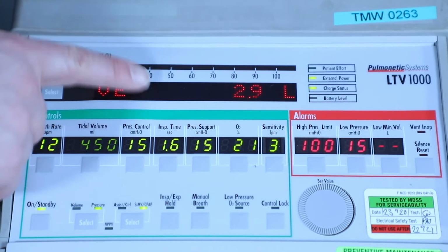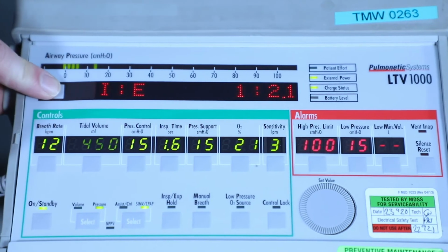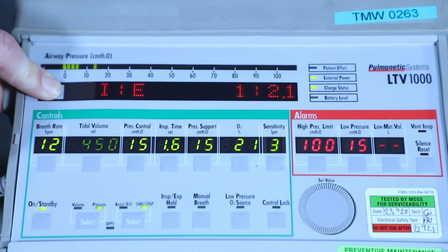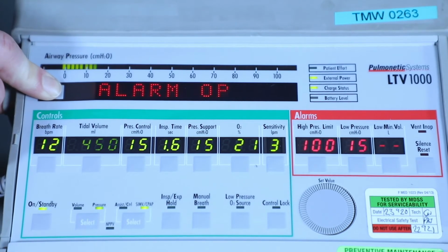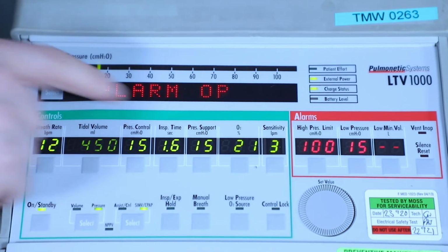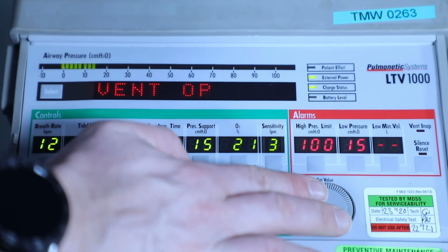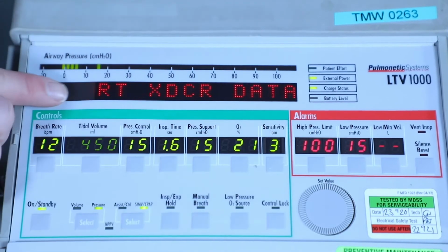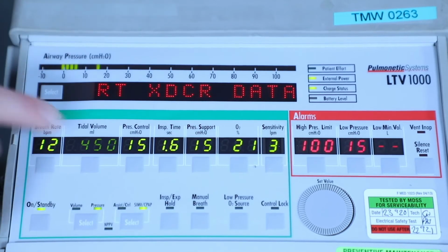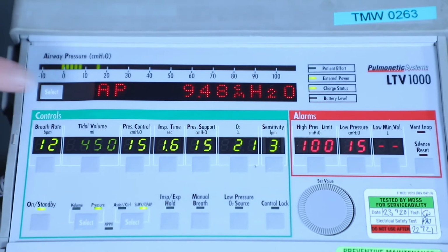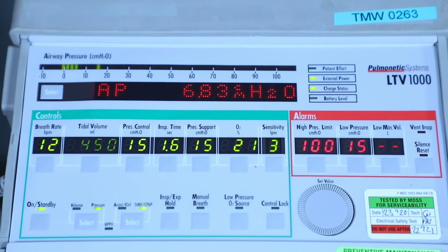So from here we want to go into the real-time transducer data, so we press and hold the select button. We keep holding this down until we come back into our extended menu options. If we scroll through, we're looking for the real-time transducer data. Press select to enter this menu. There's a few things that we're looking out for here.